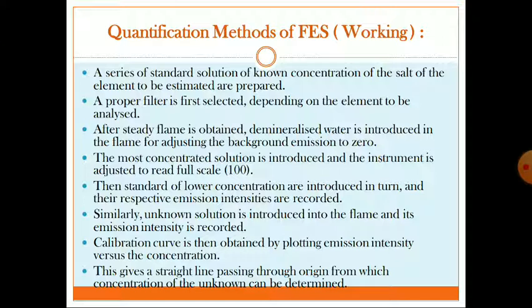After preparing the standard solutions, the third step is: after a steady flame is obtained, demineralized water is introduced into the flame, adjusting the background emission to 0. Initially we have to introduce demineralized water into the flame to adjust the background emission, so whatever unwanted emissions there are will be neglected.